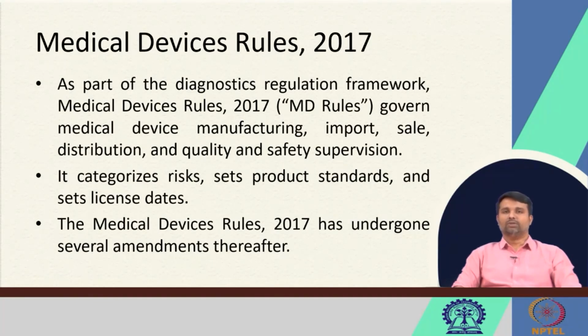The Medical Device Rules 2017 issued under the Drugs and Cosmetics Act is a significant legislation which is applicable to medical devices. As part of the diagnostics regulation framework, the Medical Device Rules of 2017 govern the medical device manufacturing, import, sale, distribution and quality and safety supervision. It categorizes risks, sets product standards and sets license dates.